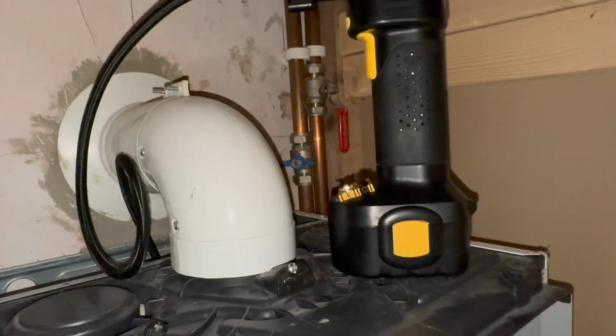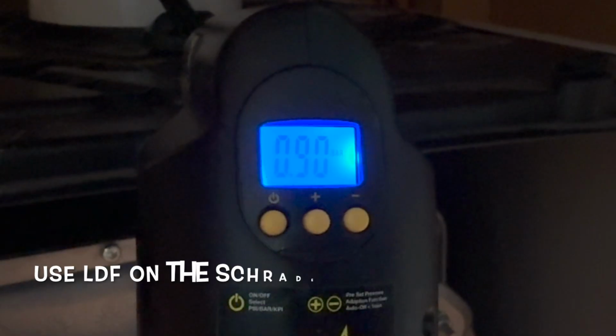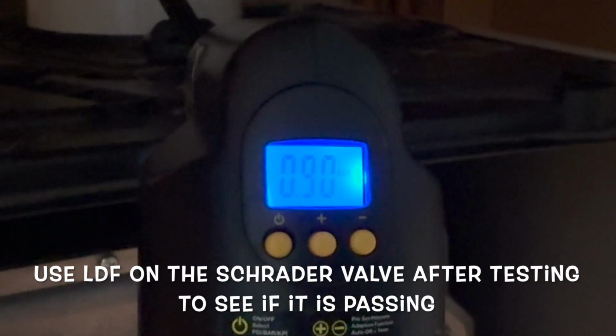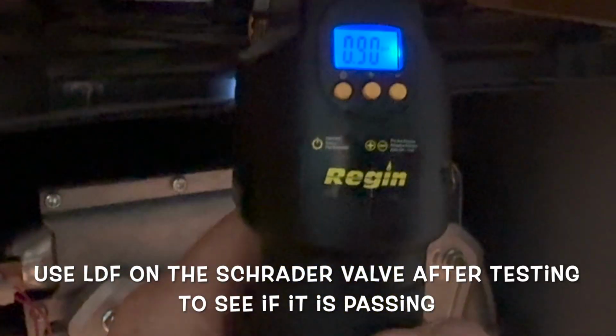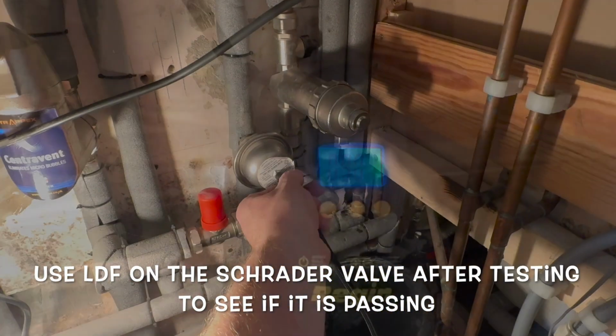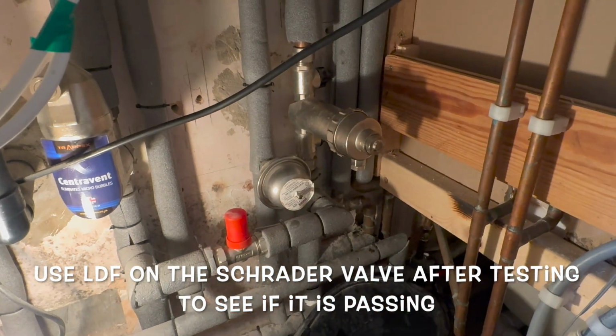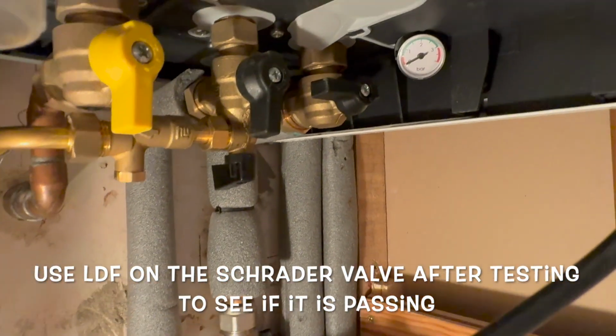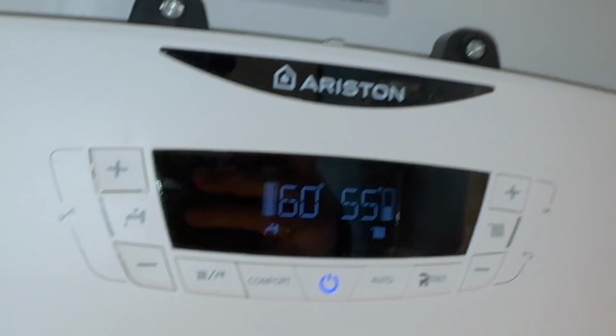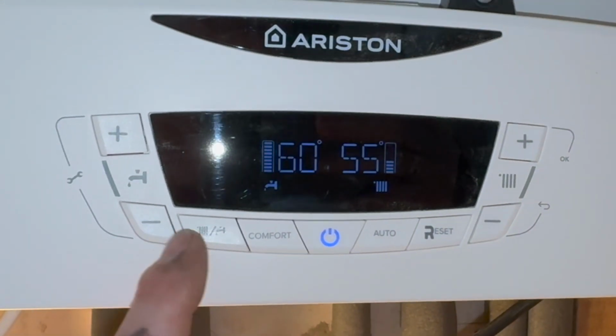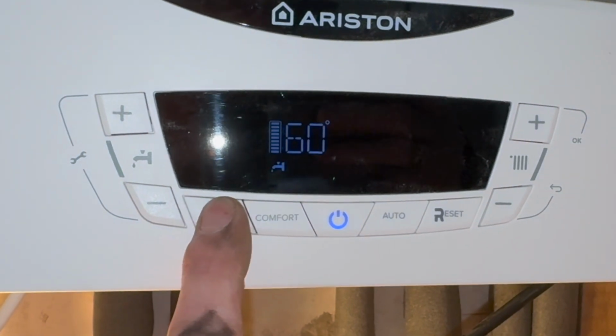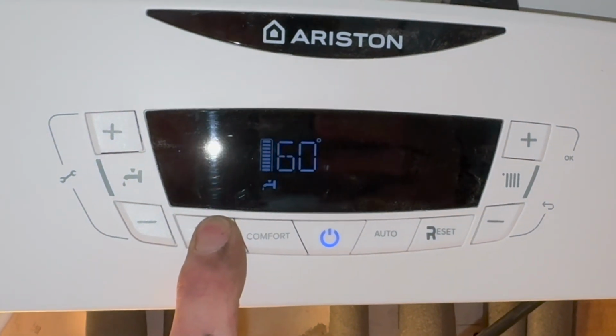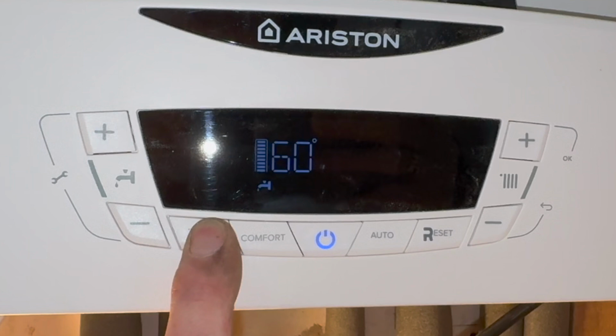So that's now screwed on there, so I can now check the pressure in the pump, and it's reading 0.9 of a bar, so that's good. All we've got to do now is test the water one and then fill it back up. So that's the water one tested as well, so all I've got to do now is top it back up. So I've topped it back up. Now this boiler has what's called a purge mode, so I can now put this boiler in purge because I've drained it basically to check the expansion vessel.